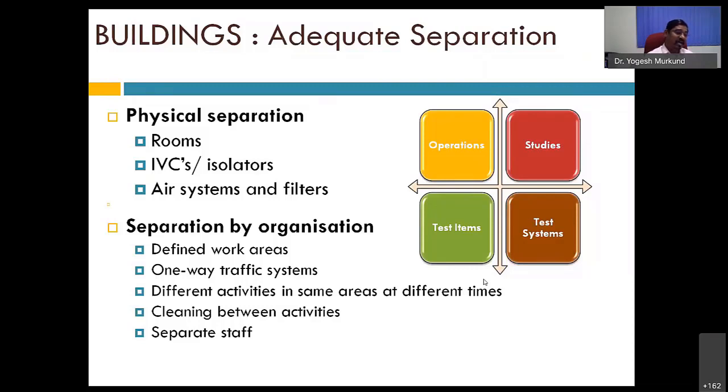or you can hold the test systems in IVCs or isolators, so that you can assure that these areas are separated by efficient air systems, which have appropriate filters, HEPA filters and those things, AHU systems.